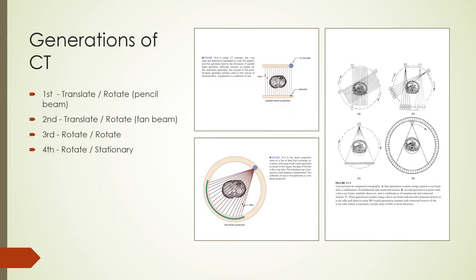In first-generation CT scanners, a narrow pencil-shaped X-ray beam was scanned across a patient in synchrony with a radiation detector on the opposite side — called translate-rotate. After collecting projections at one angle, the beam and detector rotated to a new angle and the scan repeated over a 360-degree rotation. In second-generation scanners, the pencil beam was replaced by a fan beam and a wider detector array, but the same translate-rotate approach was still used.